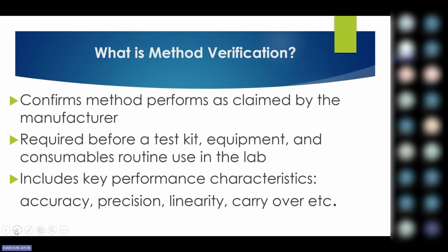This also forms part of your equipment selection. Different analyzers have different linearity limits, and you'll be able to choose equipment based on the setup of your laboratory. If you are in a cancer laboratory, you have to pick equipment that is able to pick up those extremes, extreme high or extreme low. If you pick an analyzer that has a lower linearity limit, you'll have an issue. So those particular checks will help.